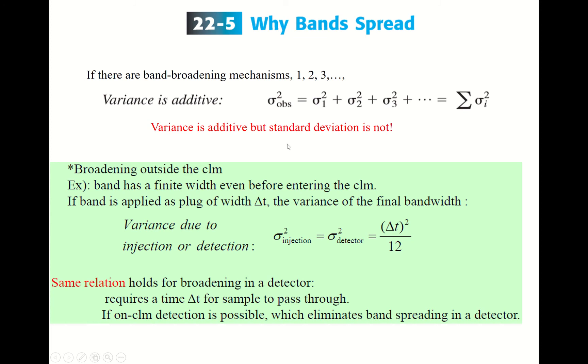Band broadening mostly occurs inside the column, but outside the column there is also band broadening. For example, the band has a finite width even before entering the column. When you inject your mixture sample with a syringe, we assume that at the moment of injection all your sample is concentrated in an infinitely thin layer at the column entrance — but actually that is not true. Band broadening takes place in the injection port.